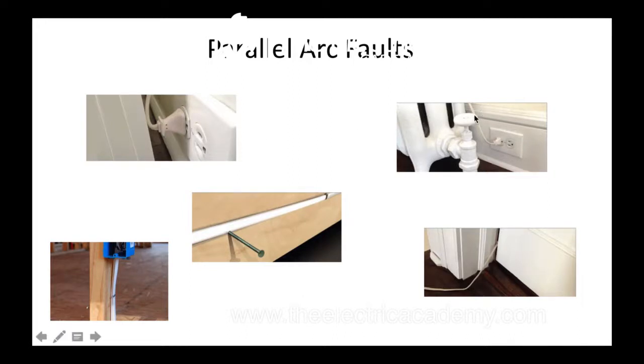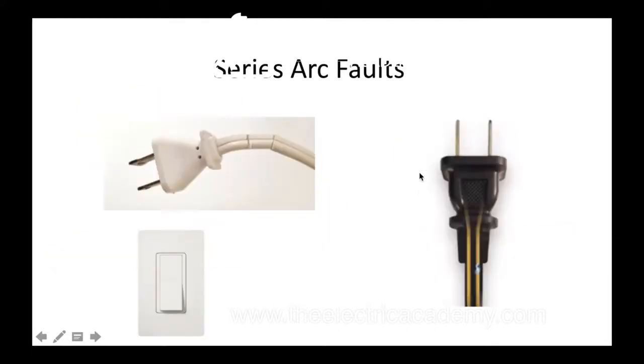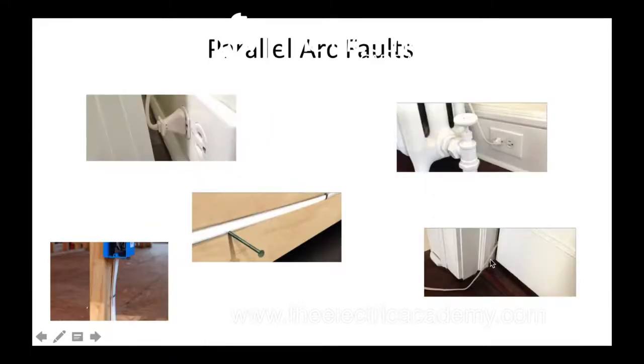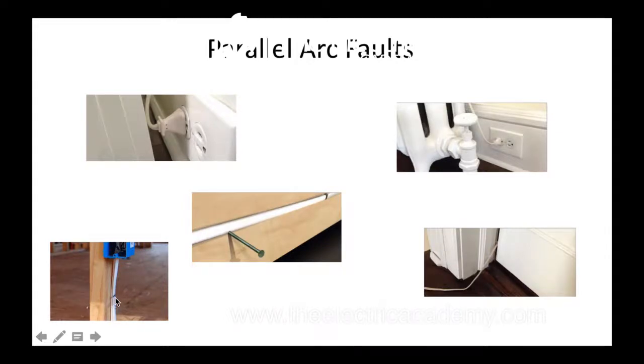Other instances include cords by a radiator — heat wrecks insulation — and sunlight will break down insulation integrity. Also, when you put an extension cord by a door and close the door on it, that pushes on the insulation, on the hot and the neutral. Nails or screws through a wire are another issue — and I'm talking to you drywallers. Also, over-stapling: when you pound that staple in too far and pinch the wire, you could wreck the insulation or cause some sort of compromise in the insulation.